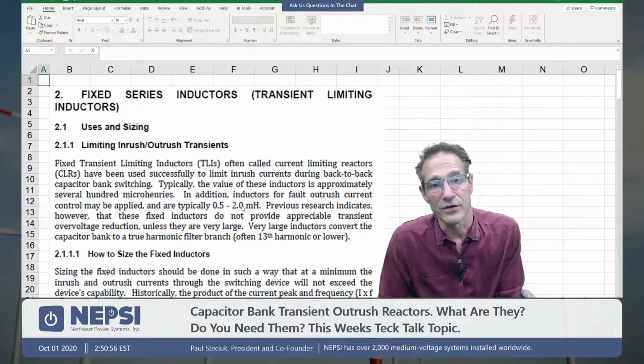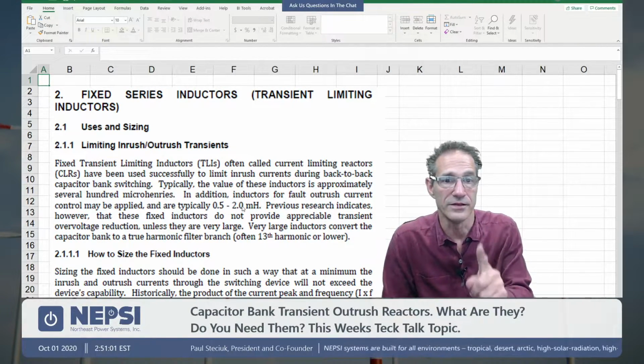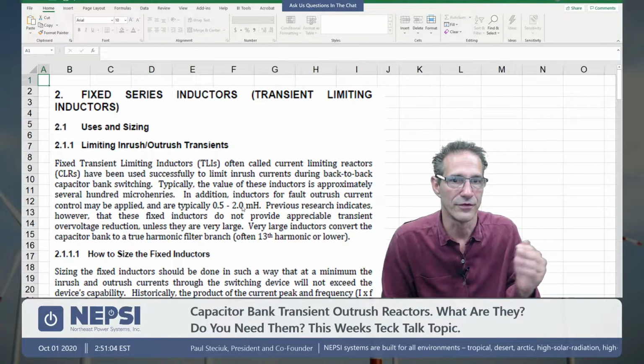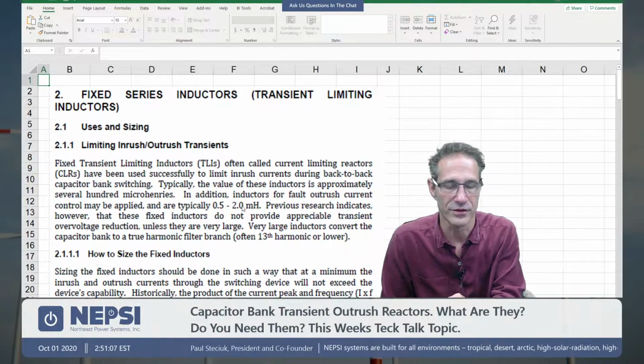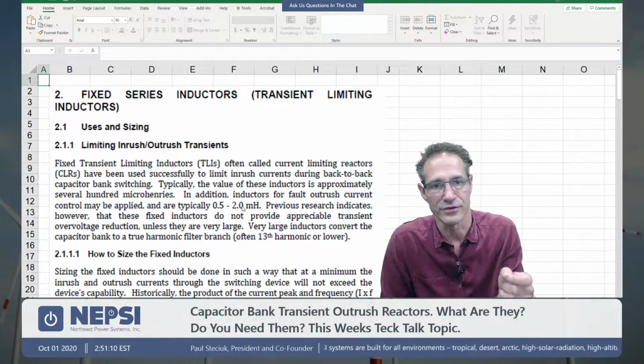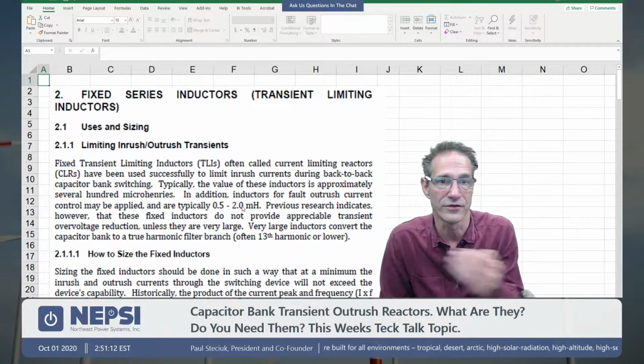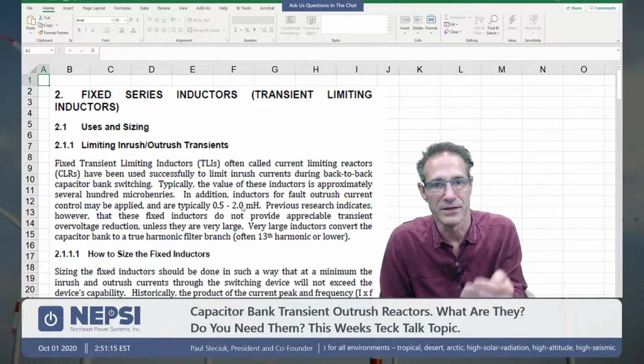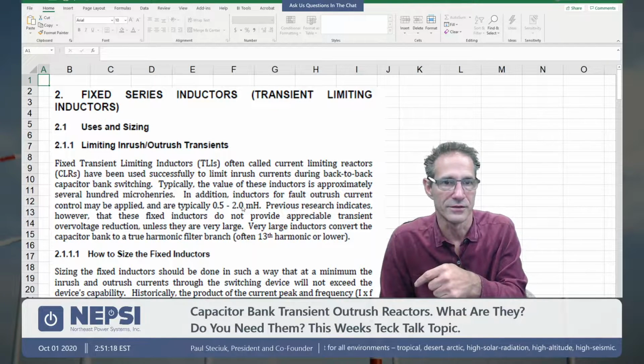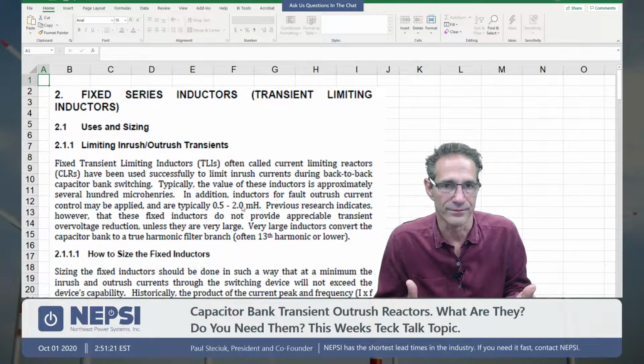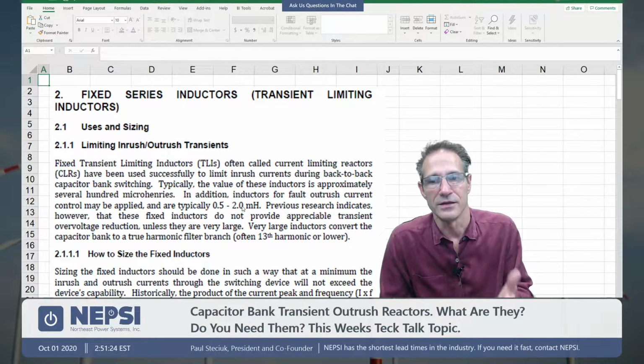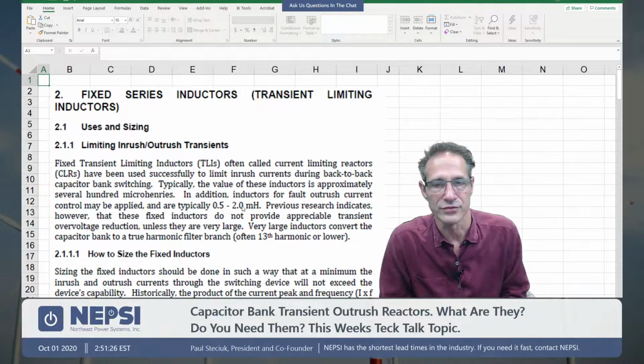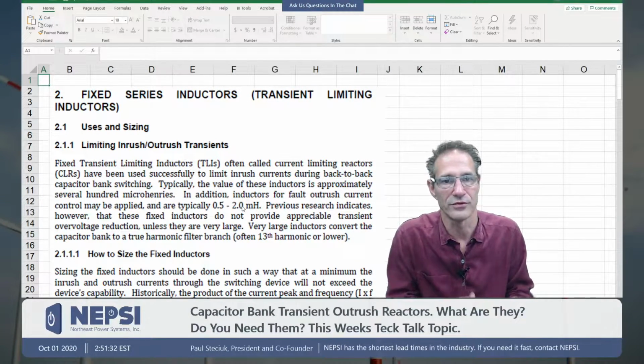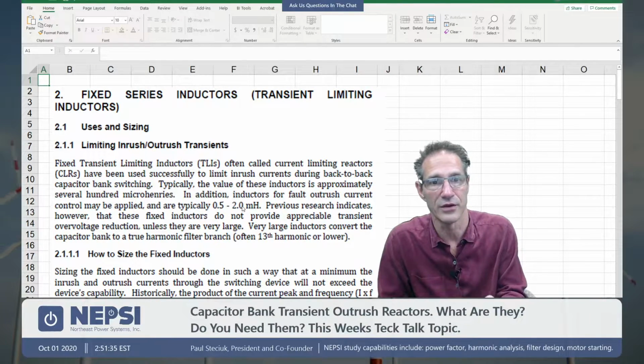And then finally, if you have outrush reactors, perhaps you can specify C1 or C2 breakers for the entire substation. What is the cost differential to put all C2 rated breakers within the substation? Okay, and if you put all C2 rated breakers within the substation, many times the outrush reactor is not required. So this is part about really understanding what the outrush current issue is, and whether there are other ways around having to put outrush reactors in a system. And one of those ways around it is C2 or C1 rated breakers in your substation. You'll get away with a higher outrush current.